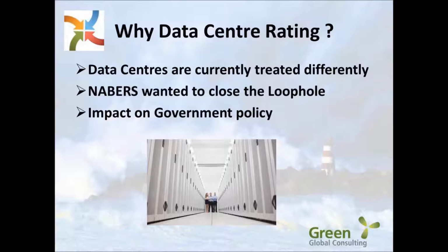NABERS now brings this into a common standard, so we can actually compare apples to apples. The other thing is there are a lot of computer rooms in office buildings. A data centre to NABERS is 10 kilowatts of heat load, which is really anywhere from 3 to 5 racks.